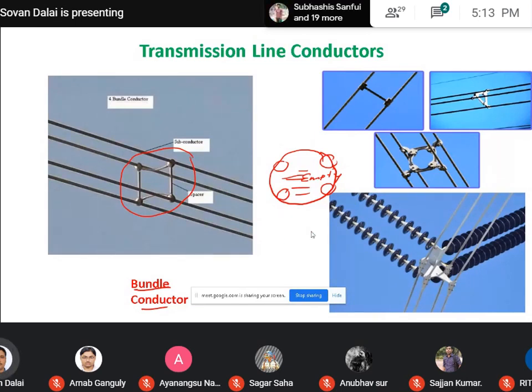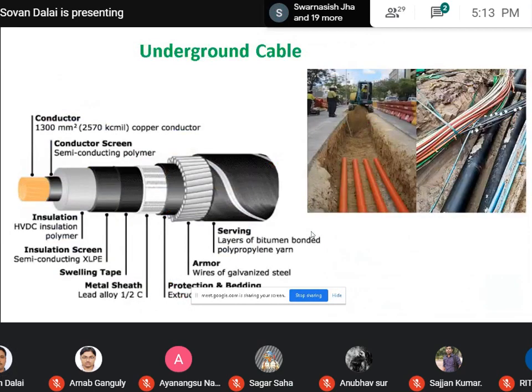Due to those reasons, we use either a bundle conductor or the standard conductor as the transmission line conductor. Another thing I want to mention is that generally we are talking about the overhead transmission line, but in some urban areas, power is transmitted through underground cable. So what is the difference between the underground cable and the overhead transmission line? Both are carrying power, but the overhead line conductor is basically a bare conductor, which is surrounded by air as an insulator.